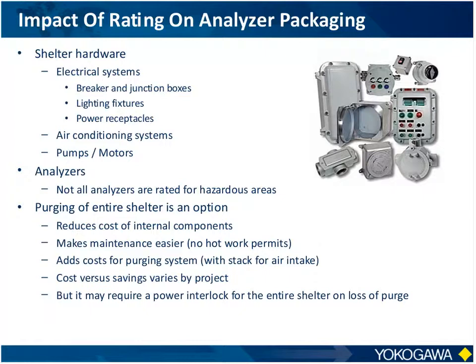It also makes analyzer maintenance easier, since technicians can turn on their laptops without worrying about violating a safety code. But keep in mind that if you lose the purge system for that shelter, you may have to interlock and turn off all power to the analyzers and equipment mounted inside. That may not be an option for mission-critical measurements, where you can't afford to shut something off just because the air got lost.